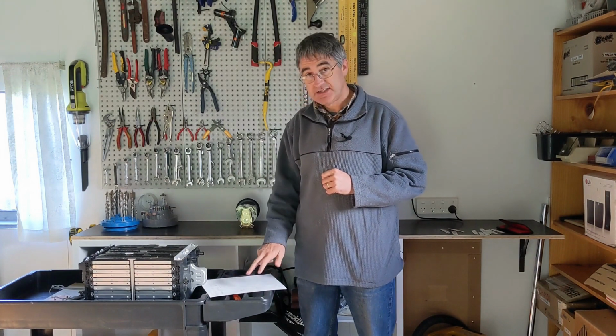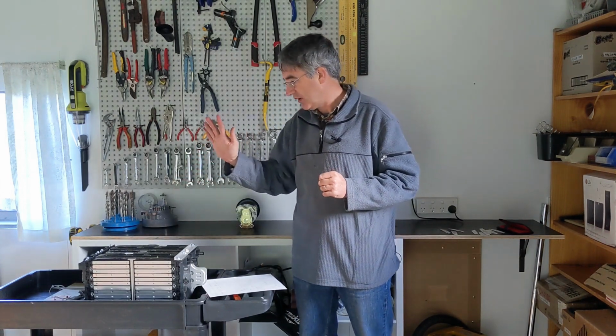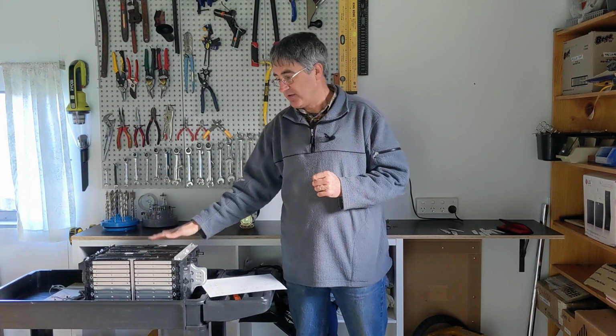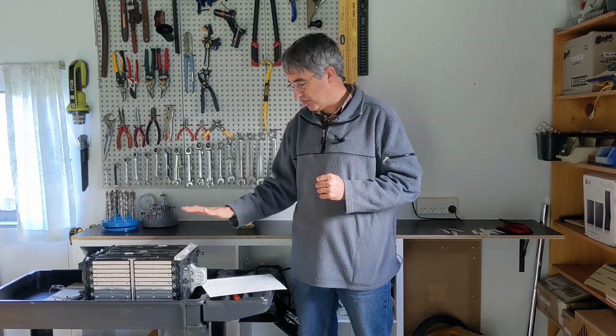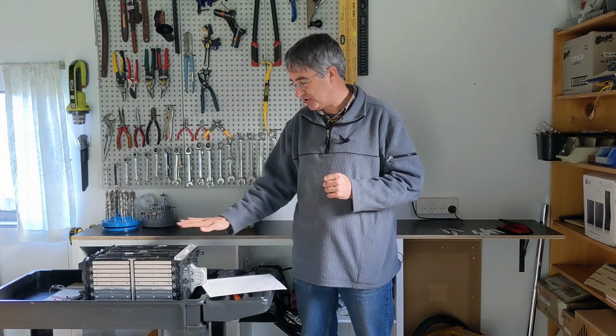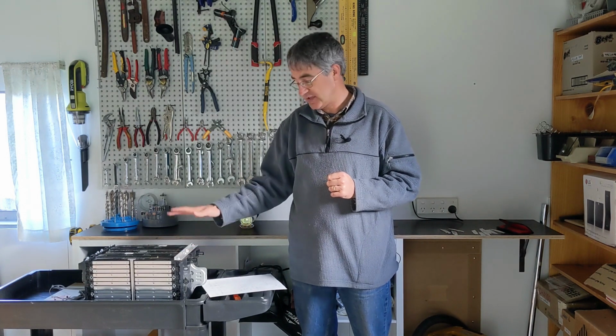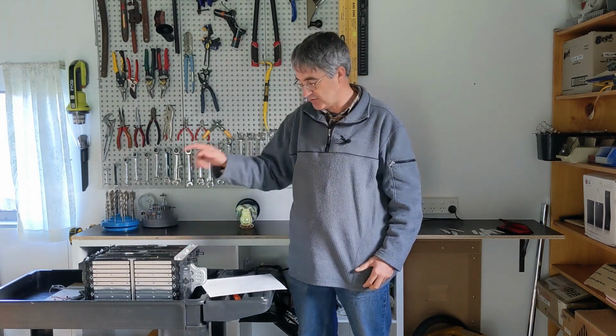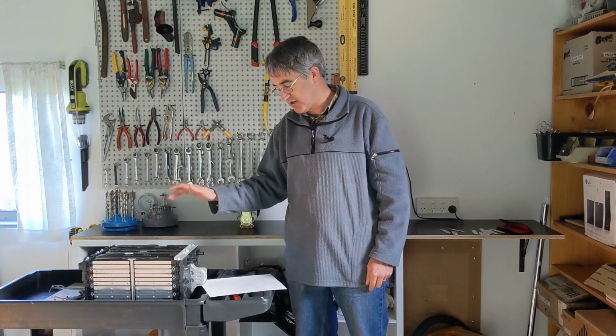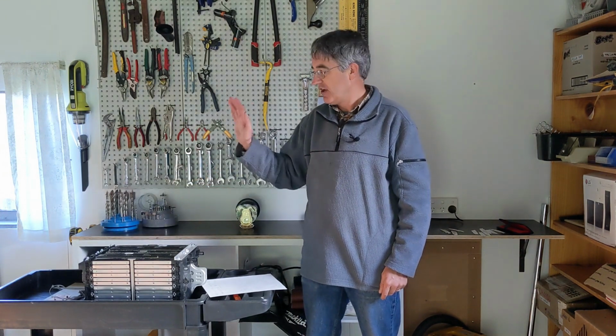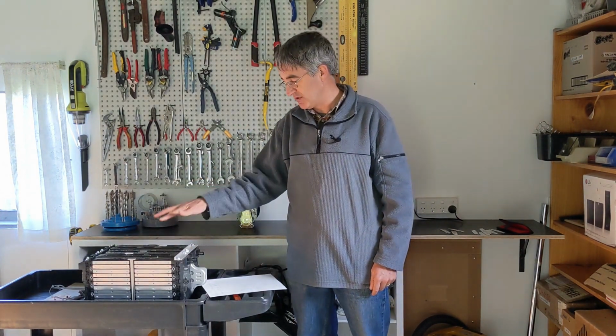Each cell voltage you can discharge to about 3.17 volts and charge to about 4.20. Each side of the battery module has a voltage of 19.0 volts up to 25.2 volts. The capacity of each side is around 2.6 kilowatt hours, meaning about 5.2 kilowatt hours for the entire module.